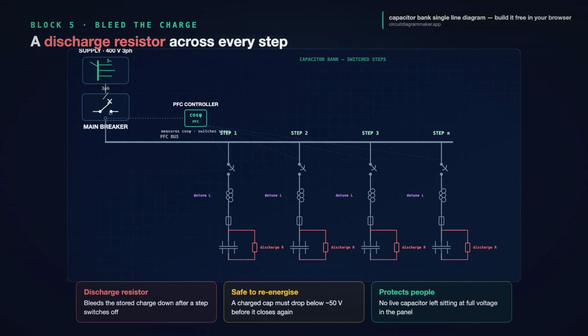Block 5, and the one people forget, the discharge resistor across every step. A capacitor does not empty itself when you switch it off. It holds its charge, sitting there at full voltage, sometimes for minutes. That is dangerous for anyone servicing the panel, and it also means you cannot safely reclose the step until it has bled down. So across each capacitor step, you draw a discharge resistor.